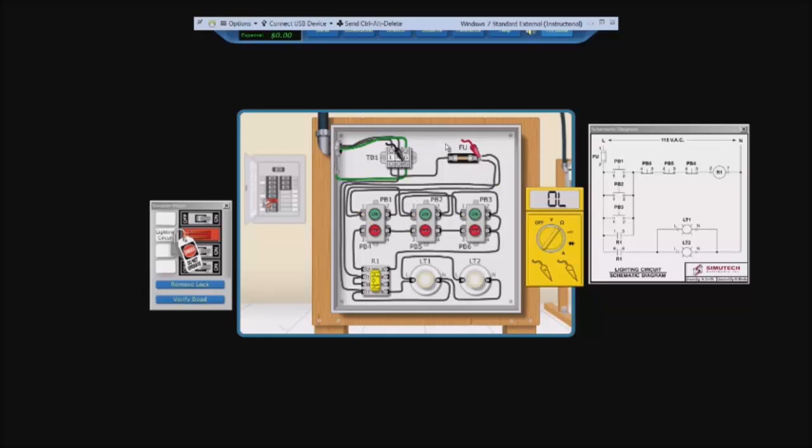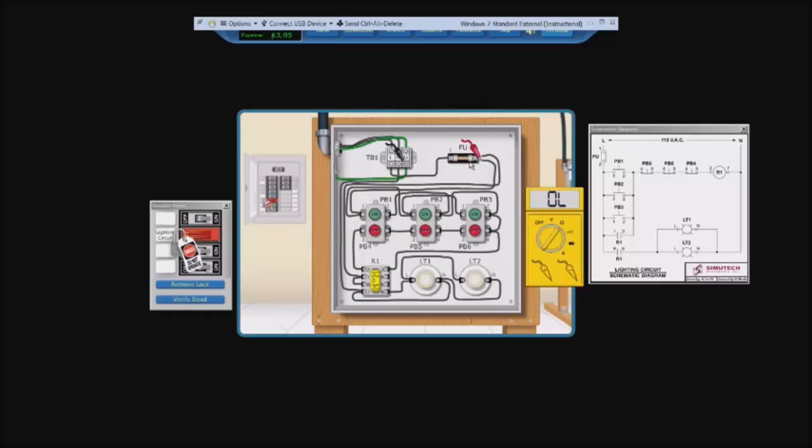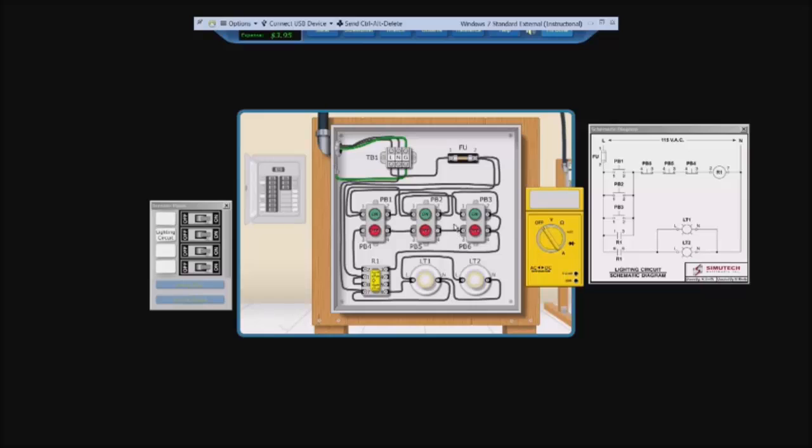So one problem that we could be having is our fuse. So let's go to our wrench and new fuse. Now, because we didn't get any resistance readings at all, I have a feeling that our fuse blew because it was faulty. So let's remove our lock, turn on power, and look, our fuse was the problem.